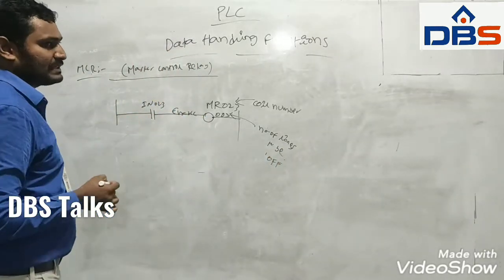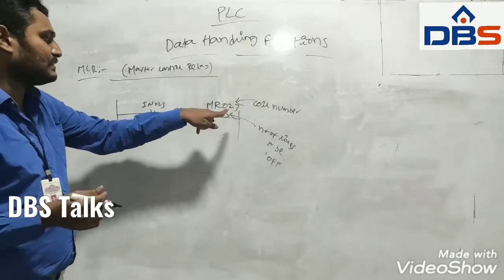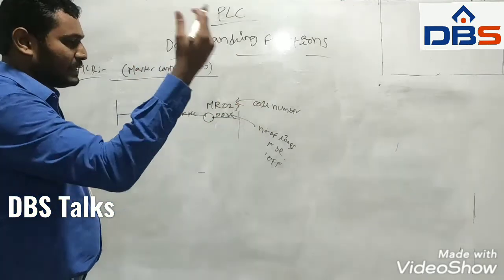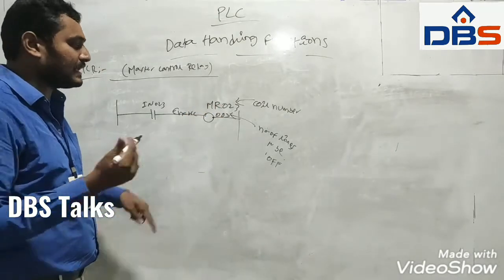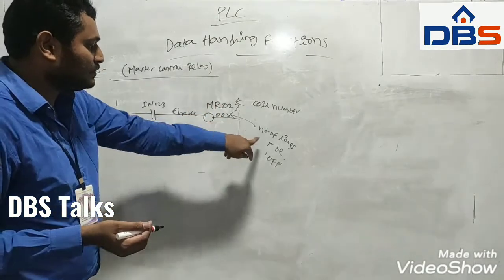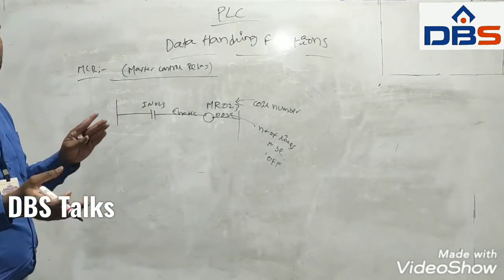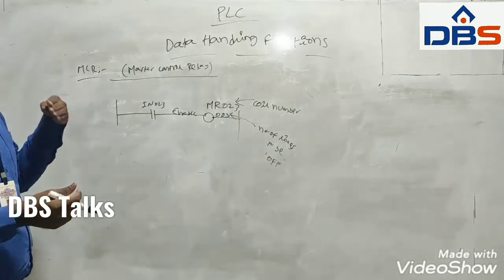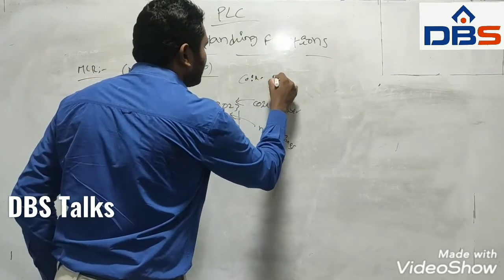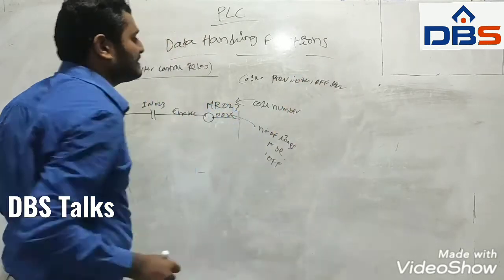According to this diagram, when the enable line is on, MCR is on, which means the process is normal. When the enable line is off, MCR is in the off condition, and at that time the 3 lines are in the off position. Compared to MCR, the skip function allows us to skip a certain portion of the program and at the same time continue the coils in their previous off state.